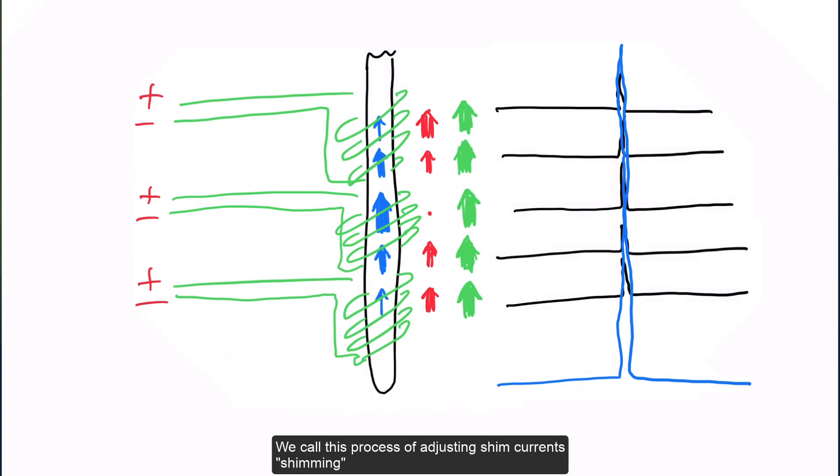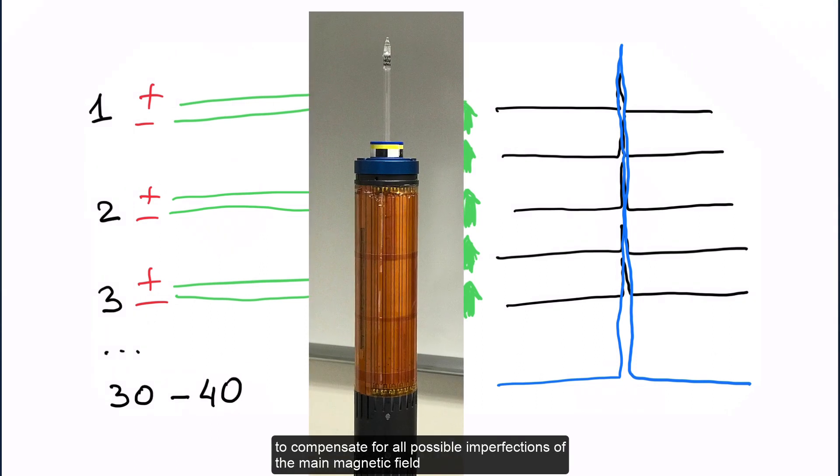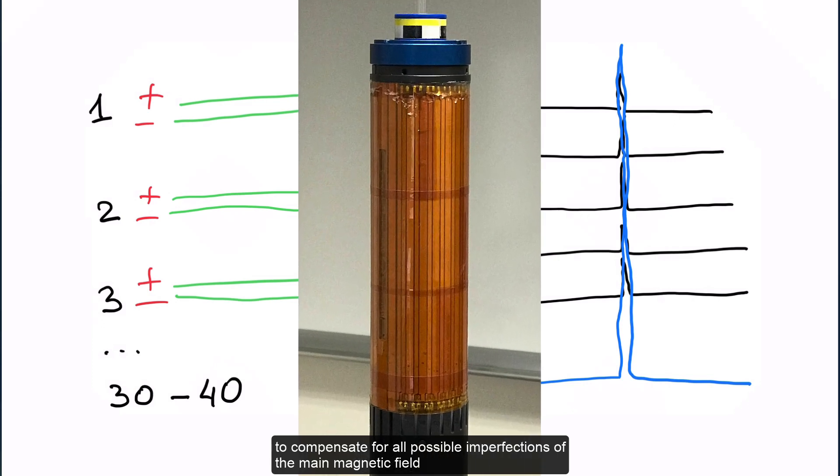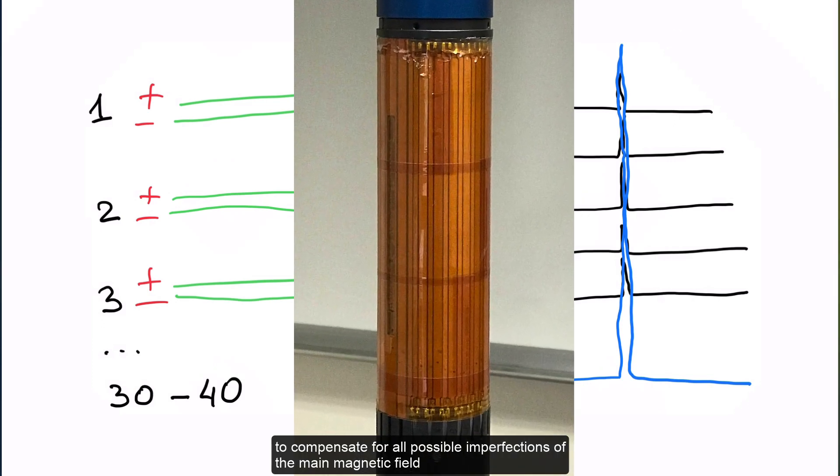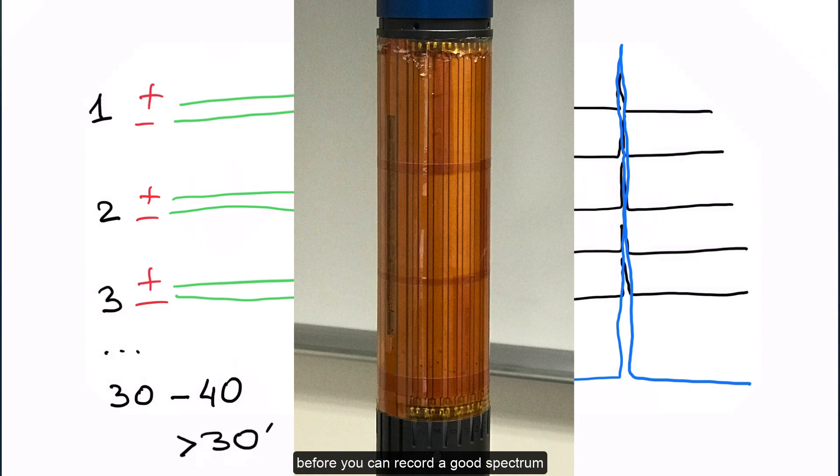We call this process of adjusting shim currents shimming. Modern magnets may have up to 30 or 40 shim coils to compensate for all possible imperfections of the main magnetic field. In the past, shimming was a part of the NMR spectroscopist's job. It could take 30 minutes to manually shim the sample before you can record a good spectrum.